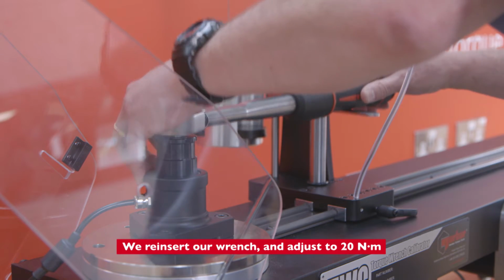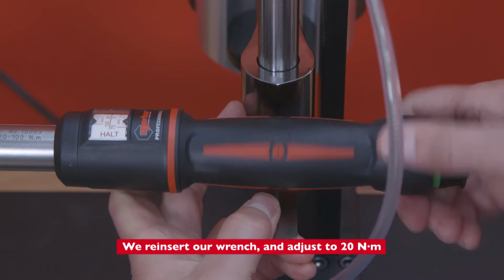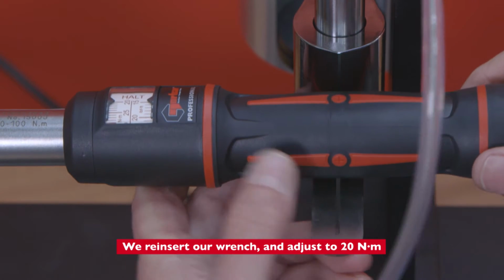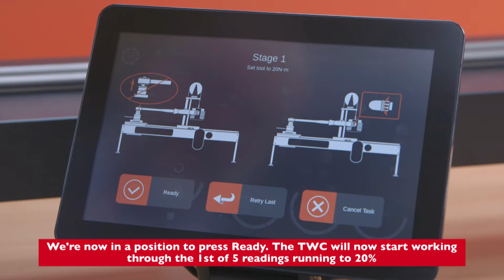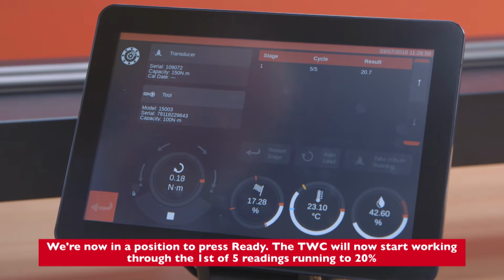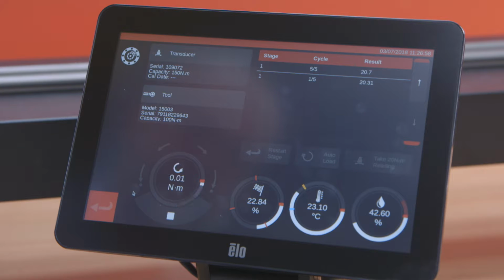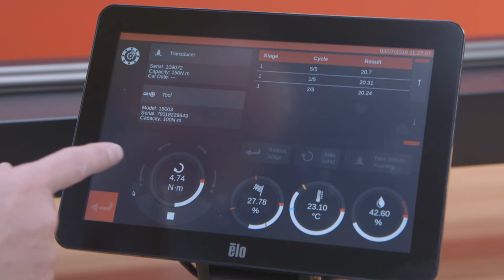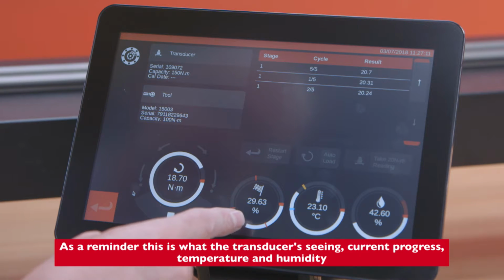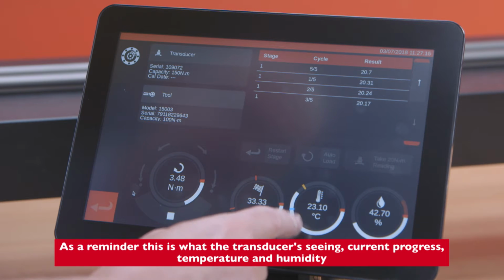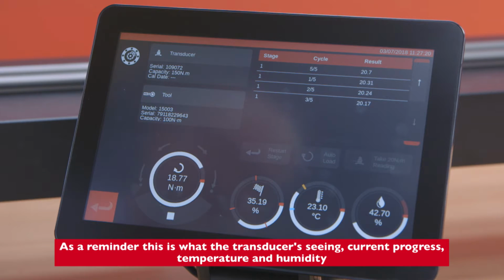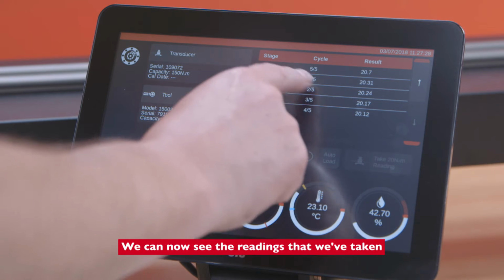We reinsert our wrench and we adjust to 20 Newton meters. We're now in a position to press ready. The TWC will now start working through the first of 5 readings running to 20%. As a reminder, this is what the transducer is seeing. Current progress, temperature and humidity. We can now see the readings that we've taken.